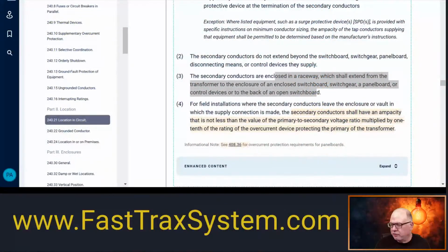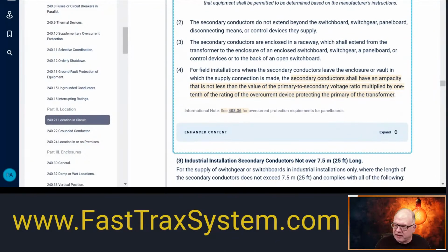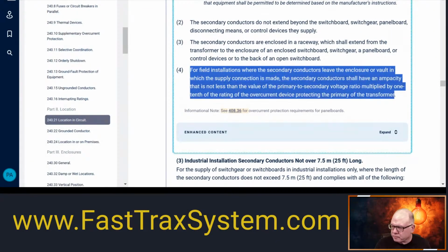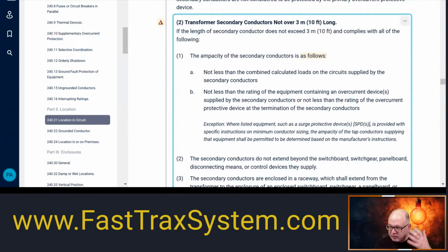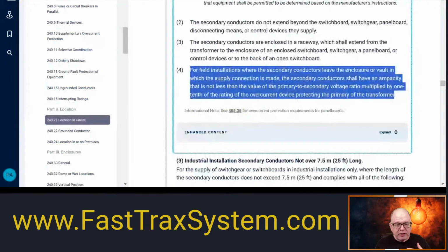So again, the intent is that from that transformer to that equipment has to be in a raceway. That's what the intent is. All right, so we followed all of that. And then the last item here is very important. Once you've done everything right and sized the conductors right, this is a rule you just have to make sure that when you're doing the installation in the field, our conductors at least meet this rule.